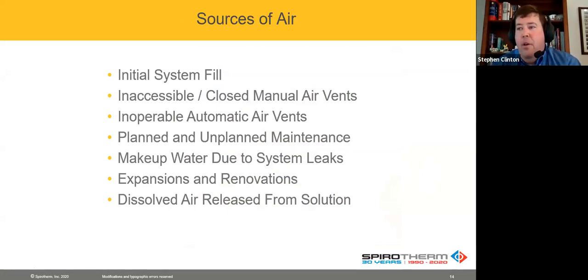How do you get air in a system? We had lots of discussions, possibly with some of you on this call, and others who've said, okay, I have a closed system. Well, okay, you get initially the system fill air, but also if you can't get to your manual air vents or some of the other automatic air vents aren't working, you're still going to have air that's there. I was just at a facility recently and we talked to some folks and they said, hey, what happens every time we bring on this new bank of equipment? What happens? Well, typically they said the contractor, it would be dry pipe and they would open up to the central chilled water system and then it would go. That's introducing raw air to a system, not even dissolved air.